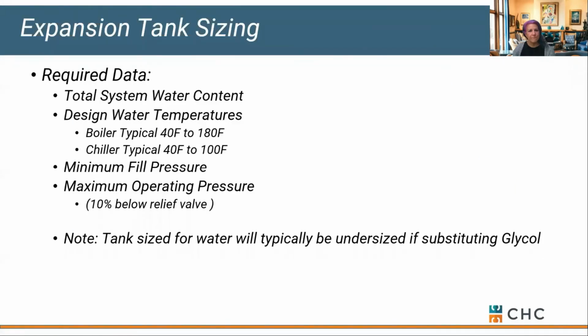Sunday, let me wrap up expansion tanks and we'll get to a question. I'm running a little behind, so forgive me. Okay. No worries. Let's talk about tank sizing. And there's 5 things we need to size a tank. The hardest one to get is this thing that we're going to call system volume. That's how much water do we have in a tank. That's a hard one to get.